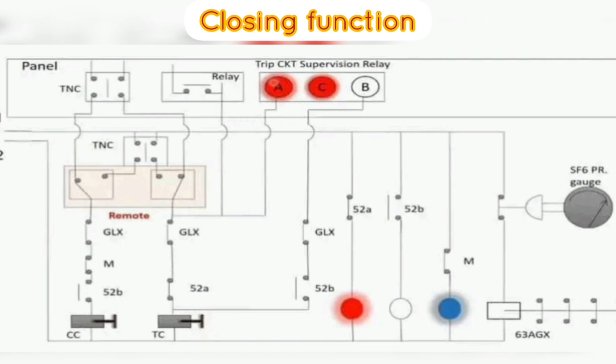Next we learn about the circuit breaker closing and tripping diagram without anti-pumping features. Closing function: the diagram shows the breaker in closed condition. When the TNC switch is operated towards close and auxiliary contact 52B remains in the NC position, the breaker gets closed and a contact changeover takes place, thus opening the 52B contact and closing the 52A contact of the trip circuit.